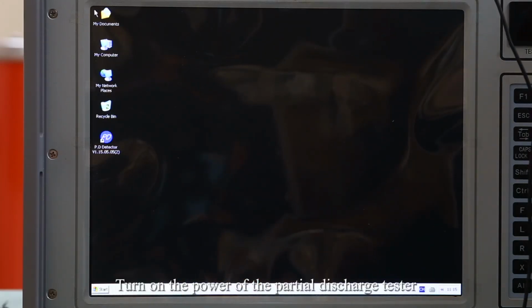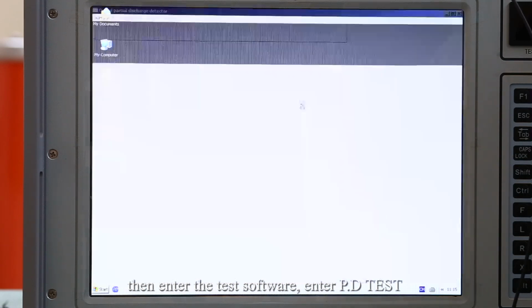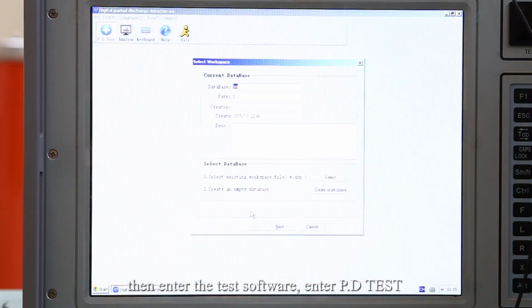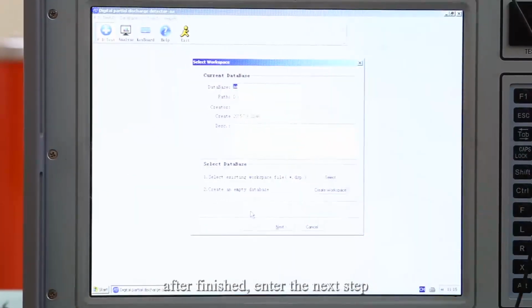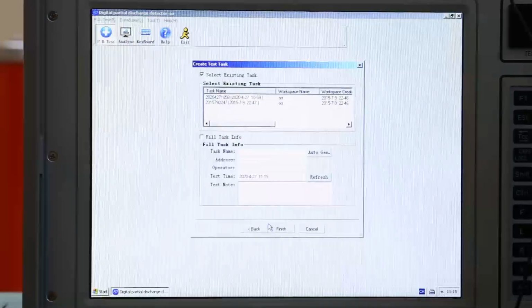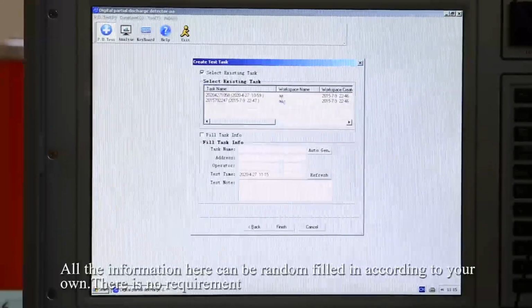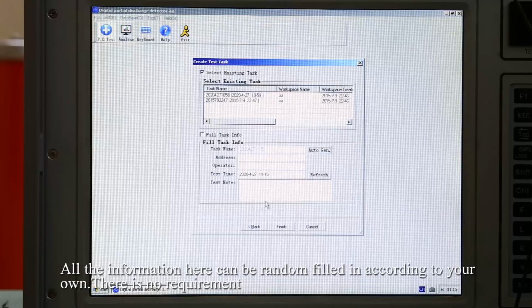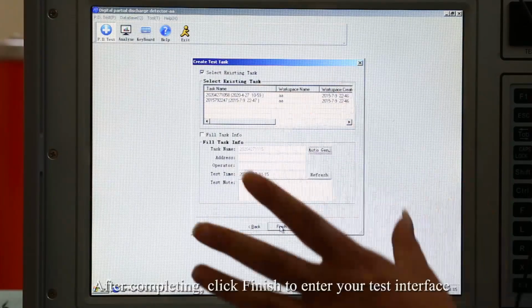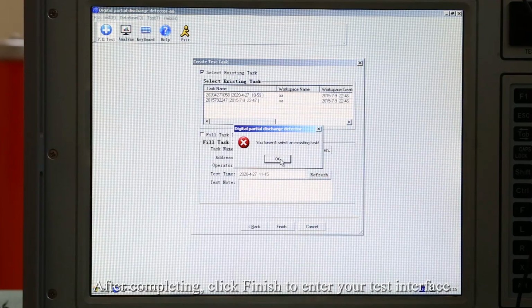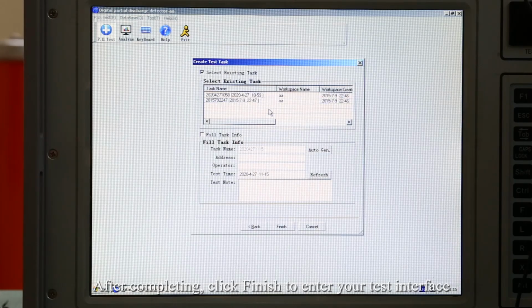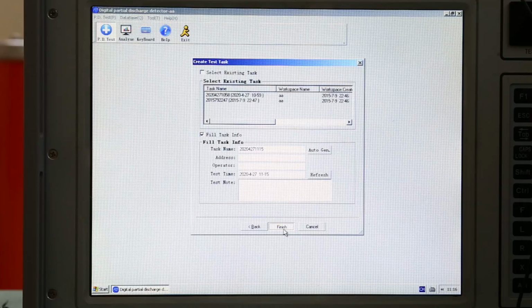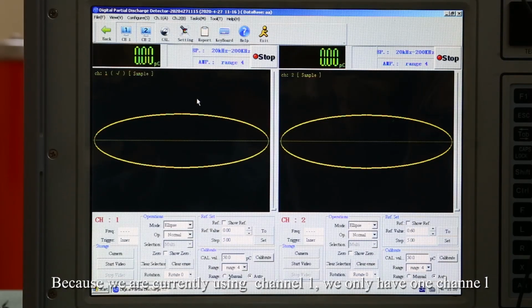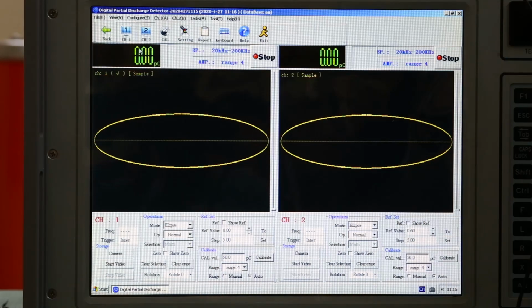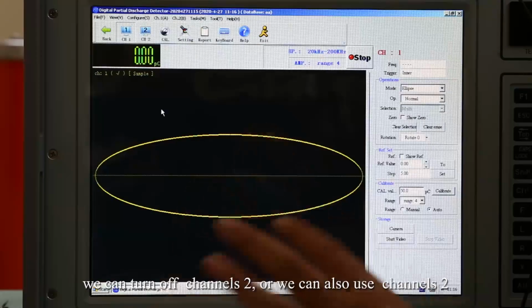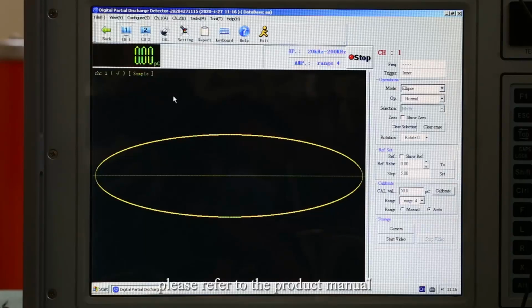Turn on the power of the partial discharge tester, then enter the test software, enter PD test. The information here can be filled in according to the customer's needs. After finished, enter the next step. All the information here can be random filled in. There is no requirement. After completing, click Finish to enter your test interface. Because we are currently using channel 1, we only have one channel. We can turn off channel 2, or we can also use channel 2. Please refer to the product manual.